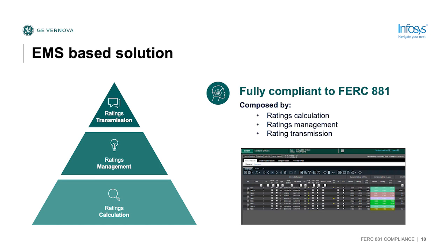So essentially the EMS-based solution is called RTOs or dynamic ratings, but it acts as the limit management system. So it enforces the limits that are in effect for both your SCADA and your network applications. It can also feed the rating sets into our multi-time point look-ahead applications. And then we also have the ability to transmit or communicate those ratings to either your neighbors or your ISOs, et cetera, all from our EMS-based solution. But it's basically the minimum that you would need for compliance, and it can pull data from your dynamic line ratings or from your ambient adjusted rating tables, et cetera.